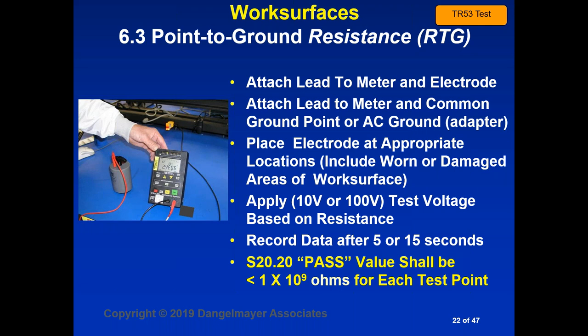Now, let me say a little bit about this pass value. S20.20 specifies 1 times 10 to the 9th. What we have found is more convenient is to say that as long as the resistance of the work surface is less than 10 to the 8th ohms, everything is okay, no action is needed. When it starts to measure between 10 to the 8th and 10 to the 9th ohms, it's an indication that maybe the surface needs cleaning, maybe it hasn't been cleaned in a long time and it's getting dirty or worn, or it may be that the table mat itself is beginning to reach the end of its life and you need to think about replacing it sometime soon.